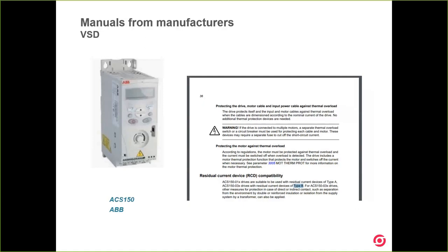Let's start with a variable speed drive from ABB — a very well-known brand. In the manual, in the part discussing residual current device compatibility, they state — and I quote textually — that ACS150-03x drives should be protected with residual current devices of type B. So it's clear: they should be protected with type B.